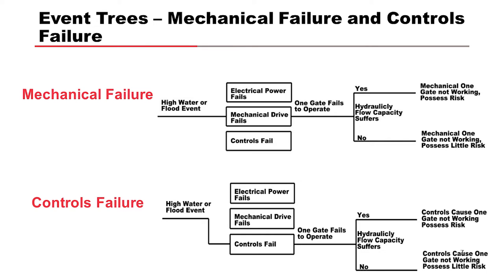Mechanical failure, too, you have to think about, typically, the mechanical hoist for a gate is independent per gate, but there are, particularly when it comes to redundant operators, there are gate hoist systems that have redundant features that are shared between gates. So, they're not strictly independent. So, it's something else you have to consider.